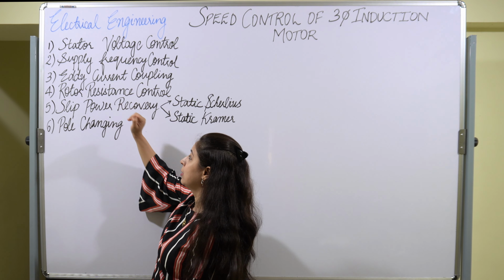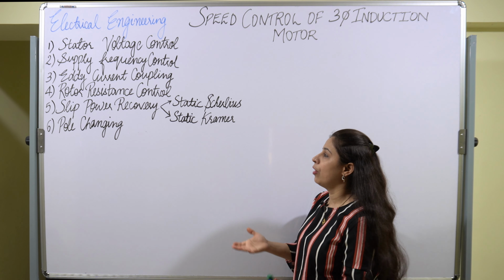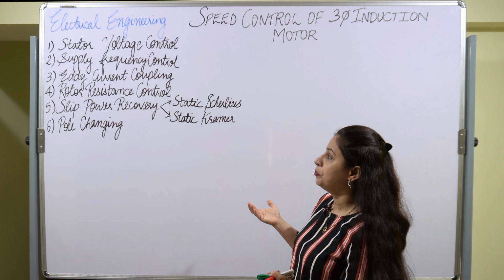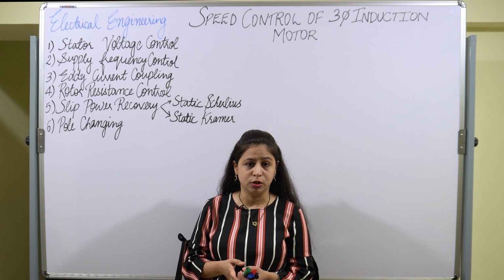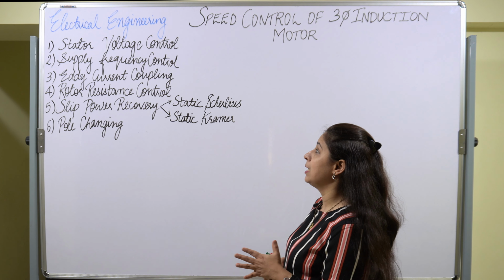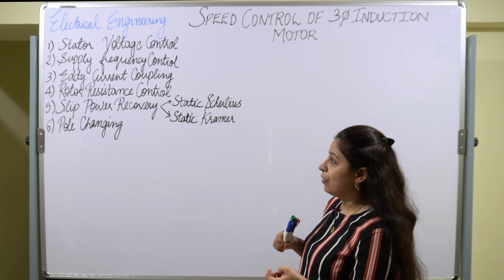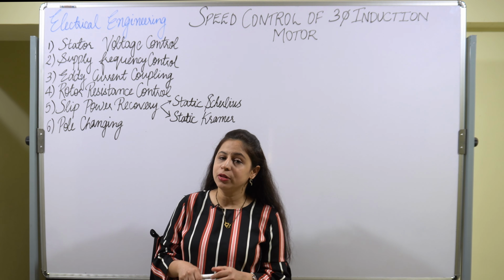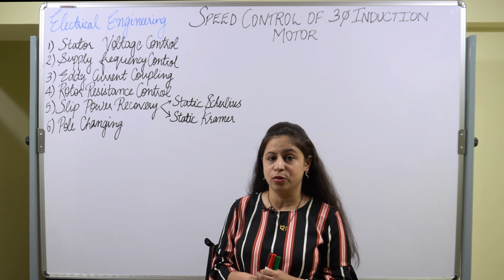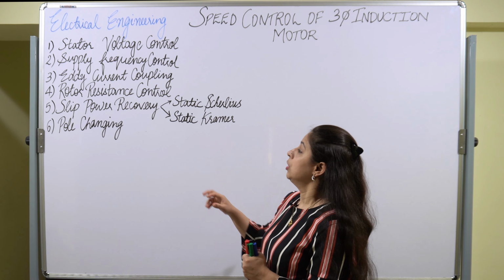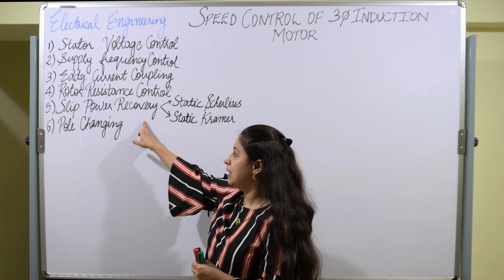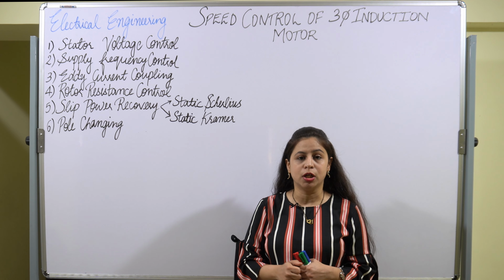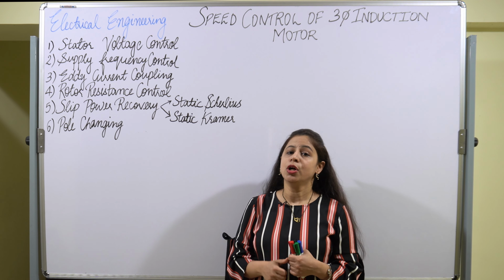Now the first three methods can be used for any type of rotor, either squirrel cage induction motor or wound rotor motor. So the stator voltage control, supply frequency control and eddy current coupling can be used for both types of rotors of the induction motor.